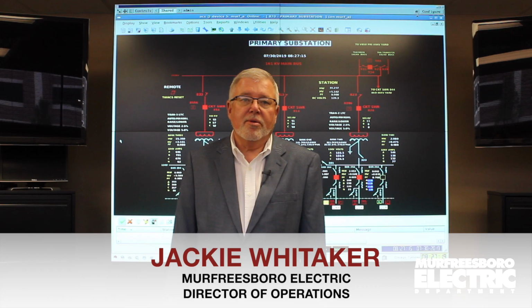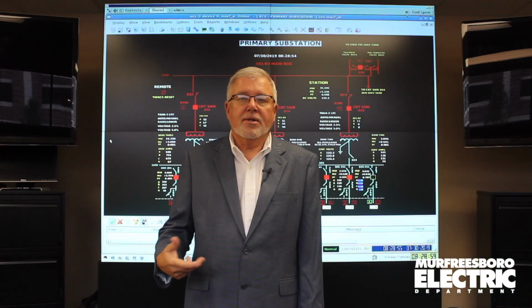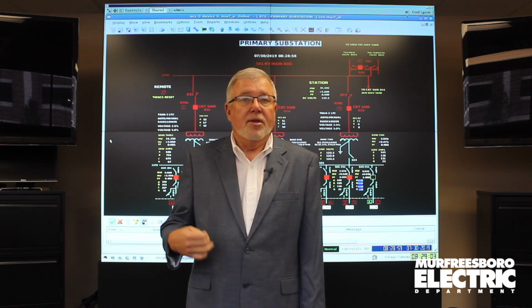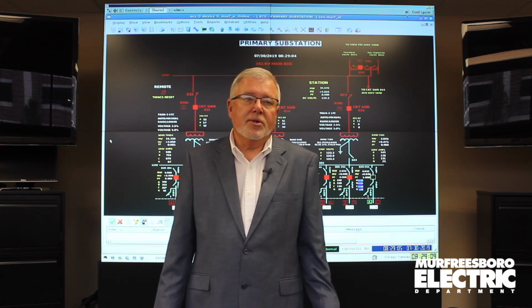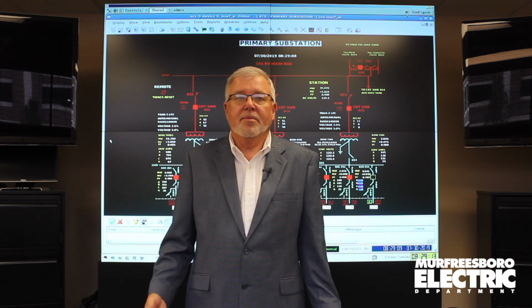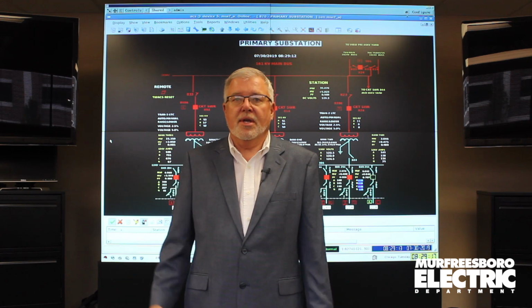I'm Jackie Whitaker with Murfreesboro Electric Department, and I'm the Director of Operations. We're the people you see out in the field. The main cause of outages on our system is some kind of contact with a high voltage line. The overhead lines you see around town are not insulated. They're up on porcelain insulators, and if you have a bird or a tree limb or a car wreck or equipment failure, it causes the electricity to seep to ground. It causes a fault, and the fault causes outages.